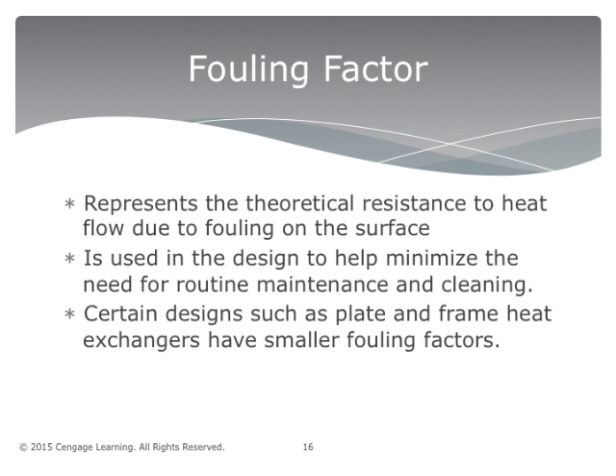So how can fouling be prevented? Routine maintenance, such as cleaning or replacement of old parts, such as pipes, will help reduce the fouling that is occurring in the system. Certain designs, such as plate and frame heat exchangers, may also be implemented. These heat exchangers have smaller fouling factors than other heat exchangers. This is because they have smoother surface areas to keep the deposit of minerals and other solids from forming. These heat exchangers also keep a high degree of turbulence in the flow, keeping the solids in suspension and thus further reducing fouling on the pipe.